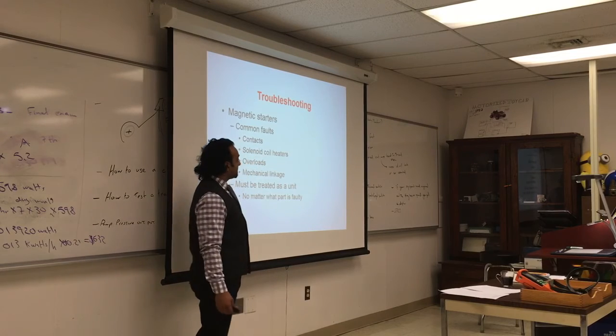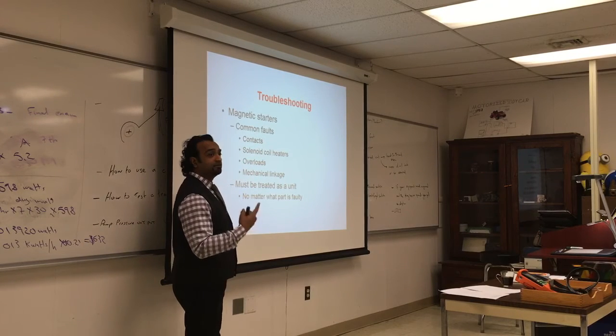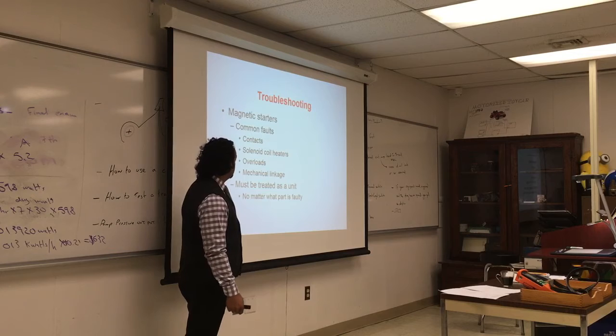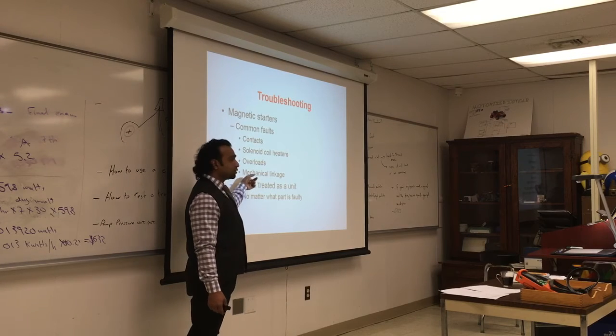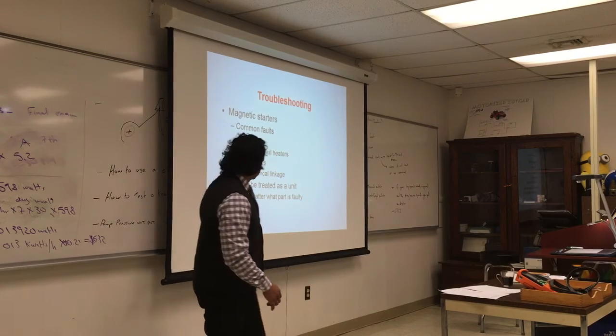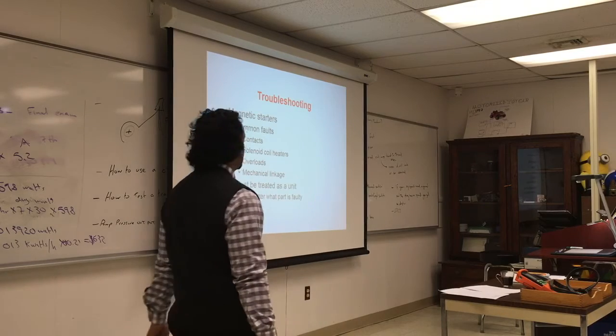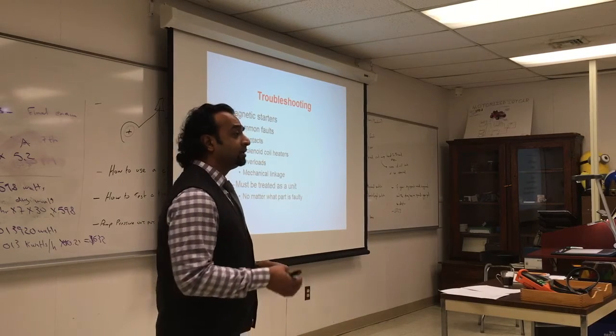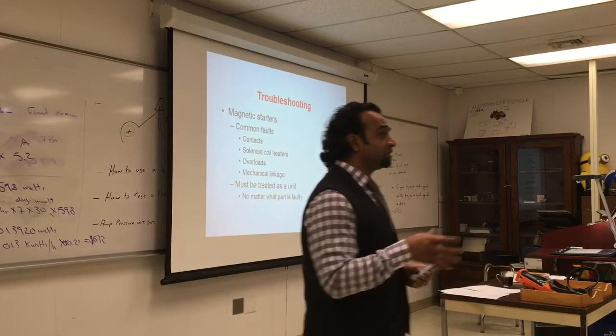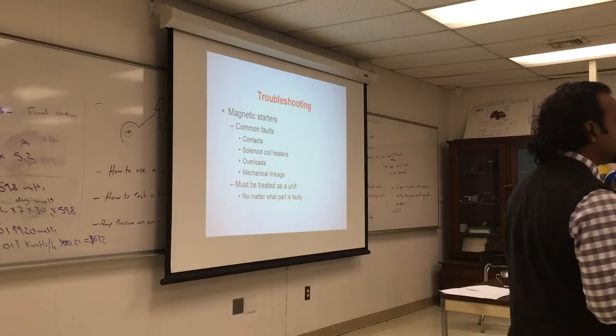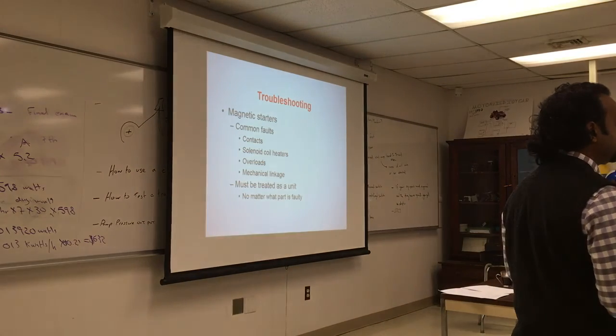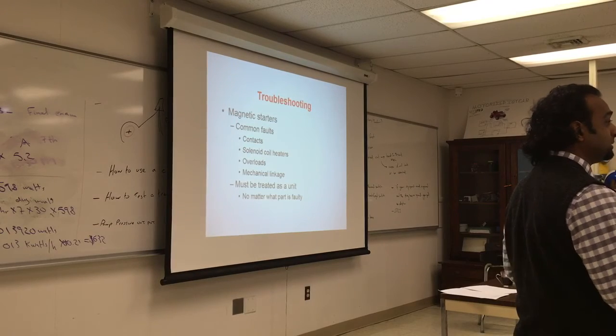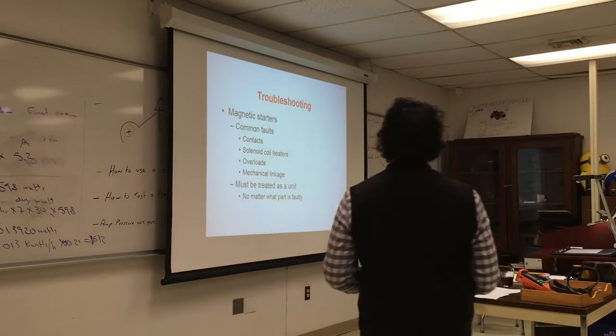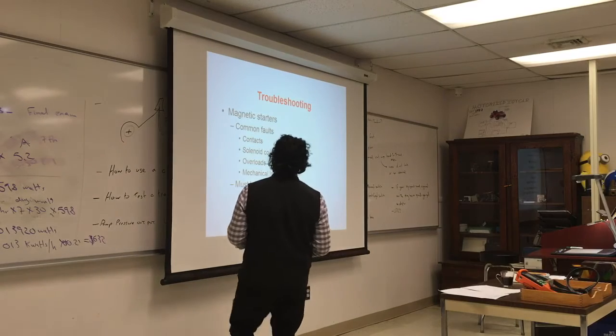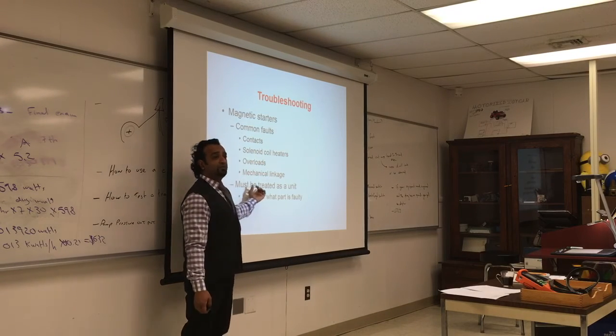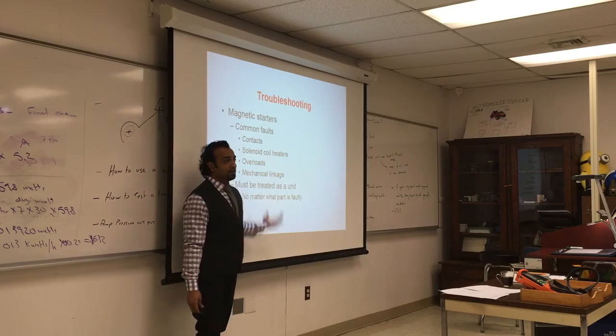Solenoid coil heater. So look at the solenoid visually and also test for continuity. Look for overloads and also for mechanical linkage. You test the magnetic starter unit completely, don't take it apart. Again, they are manufactured in a certain environment, and they are put together with certain clearances between the parts, so you do not have to take it apart and put it back again. It must be treated as a unit. Whatever breaks in it, you replace the entire unit.